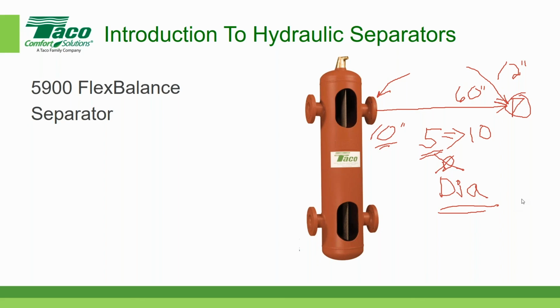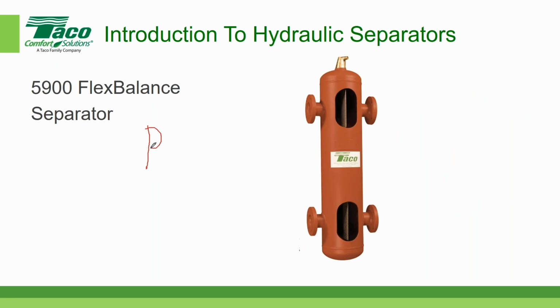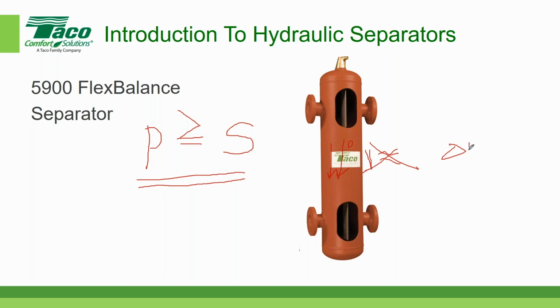In other words, our ideal condition is when the primary is equal to or greater than the secondary. Under that situation, if the primary is equal to the secondary, then there won't be any flow. There'll be zero flow across the bridge in this direction here. When the primary is greater than the secondary, then you'll get some flow across the bridge. And whatever flow you get across that bridge, the delta P wants to be approximately equal to 0 whenever there's flow across the bridge.